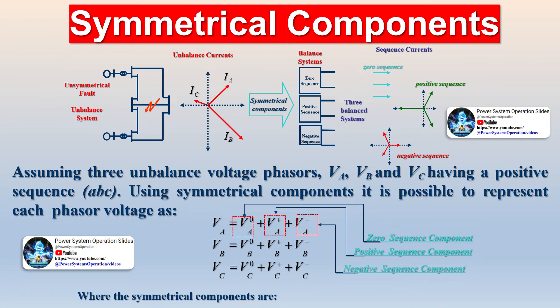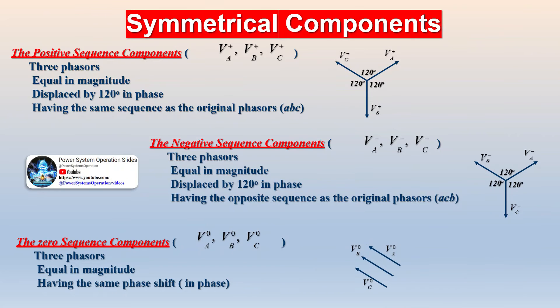Equipment protection: Symmetrical components aid in designing protective relays for equipment. By analyzing the magnitude and phase relationships of the positive, negative, and zero-sequence components, engineers can set appropriate relay settings to detect faults and adjust the burden in instrument transformers to protect equipment from damage.